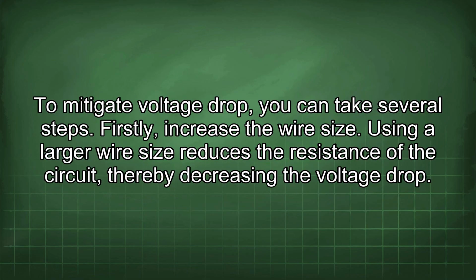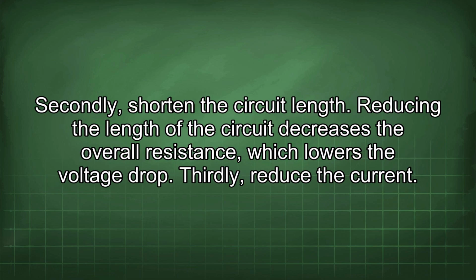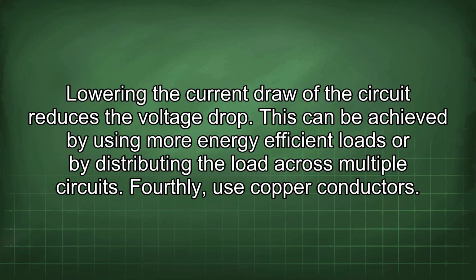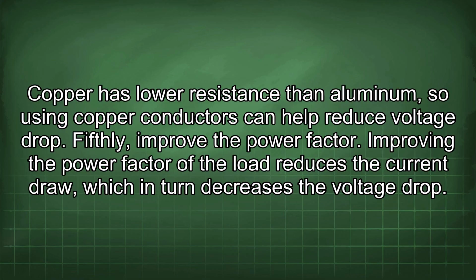To mitigate voltage drop, you can take several steps. Firstly, increase the wire size. Using a larger wire size reduces the resistance of the circuit, thereby decreasing the voltage drop. Secondly, shorten the circuit length. Reducing the length of the circuit decreases the overall resistance, which lowers the voltage drop. Thirdly, reduce the current. Lowering the current draw of the circuit reduces the voltage drop. This can be achieved by using more energy-efficient loads or by distributing the load across multiple circuits. Fourthly, use copper conductors. Copper has lower resistance than aluminum, so using copper conductors can help reduce voltage drop.